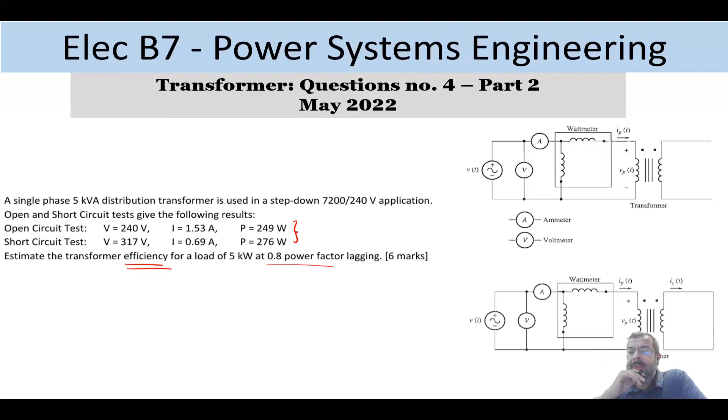I will put them in the video description. So the open circuit test, basically, we apply the rated voltage. Now this transformer is 7200 by 240 volt. So we apply the rated voltage. We can theoretically apply this voltage or that voltage while the other side is open circuit. Now because practically, it's easier to have a generator that can supply the low voltage than the high voltage, so usually in practical, this is how we do it. We apply the rated voltage of the low voltage side. And that is how the manufacturer does it, actually.